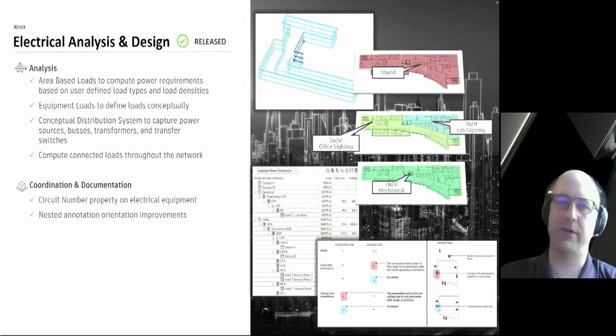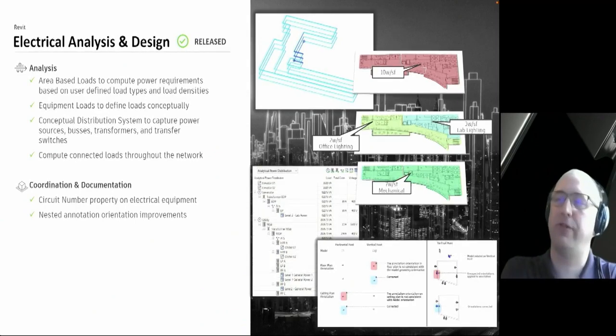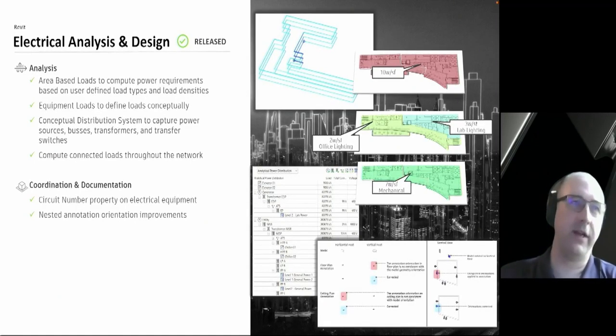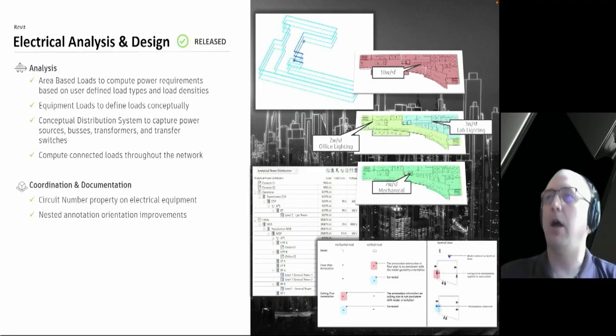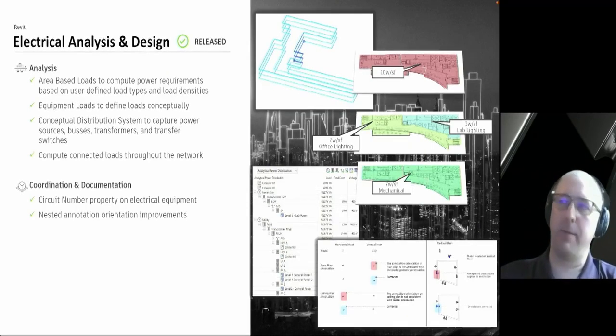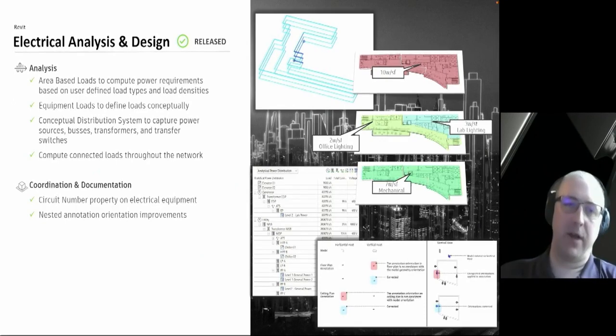The first is this idea of area-based loads, where you can define over the floor plate - whether it's a linked Revit model, a linked PDF, or DWG - and create these area-based elements. Assign that area-based element to a load classification, whether for lighting of different types, mechanical services, or general power, assign it a power density, and use that as the basis of a load takeoff.